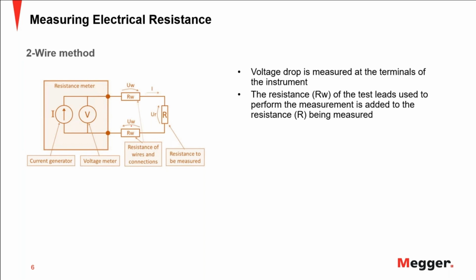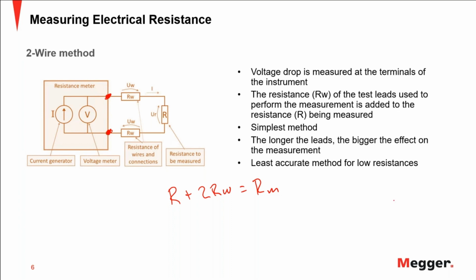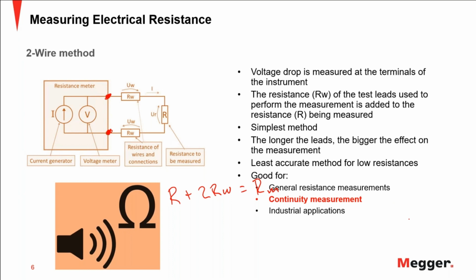And if you use the two-wire method, the voltage drop that you are interested in measuring is measured at the terminals of the instrument. So in your result, you are going to get not only the resistance that you are interested in, but twice the resistance of each of the leads. So that's going to be your total resistance, or your measured resistance. So you're not going to get an accurate value. This method is the simplest method to use to measure a resistance. But the longer the leads, the bigger the effect on the measurement, and it's the least accurate method for low resistance measurement. So it is good for continuity, but definitely not the best method for low resistance measurements.